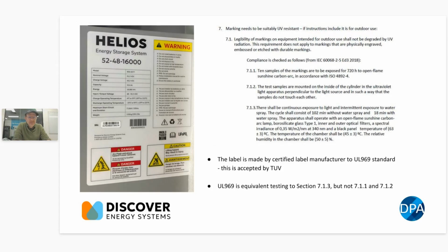That normally works, but with the CEC best practice guide, they've got extra clauses about it being mounted on a cylinder in ultraviolet light and tested for a certain number of days and a certain number of samples, which I think references a different standard. So they just need to get a piece of paper saying it meets that standard as well. It's all pretty dry and boring, but the only reason I'm mentioning it is that it's not that they think there's a problem with the design or the IP rating or anything like that.